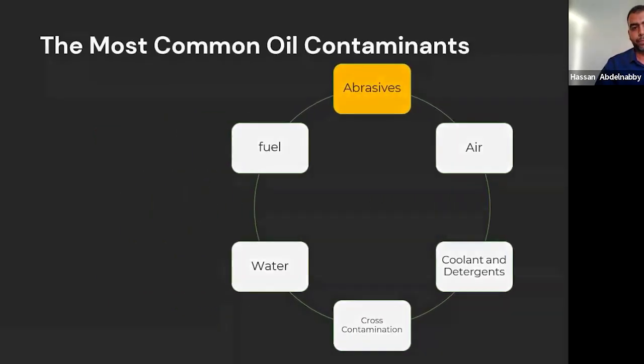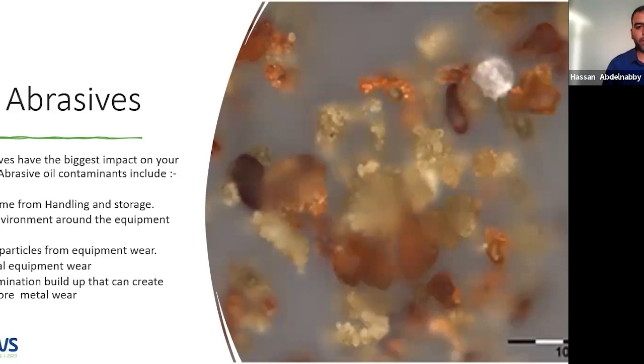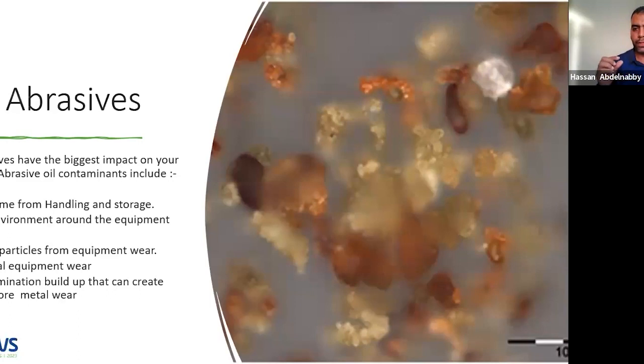Abrasives are a huge enemy. Dust can come to your equipment from the environment — I work in a tissue mill, so we have fine dust from the pulp itself that can contaminate our lubrication units. It can come from storage, handling, transportation — every aspect of the environment is trying to get inside your equipment. Metal particles can come from normal wear, but some build up and fit inside the oil film, creating a three-body abrasion that increases the wear rate of the metal itself.